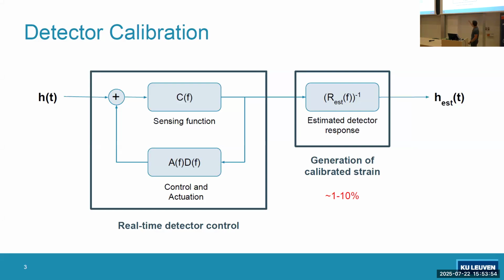That's a situation where the C block just tells you, okay, this is some sensitivity of your photodetector that measures the interference pattern, and then I have to compensate with an amplitude factor, and I have my strain. But it turns out that this function itself already is not just a flat function. It has different parameters, and it has a shape in frequency, so you have to account for that. But then additionally, there's another thing that people have to do, and that is that we want to keep the detector in resonance. So we measure this interference pattern, the strength of that signal, and then based on that, we pass that through a digital filter, which is designed by instrumentalists, to calculate some actuation signals. And those actuation signals are then used to push the mirror back to its equilibrium position.